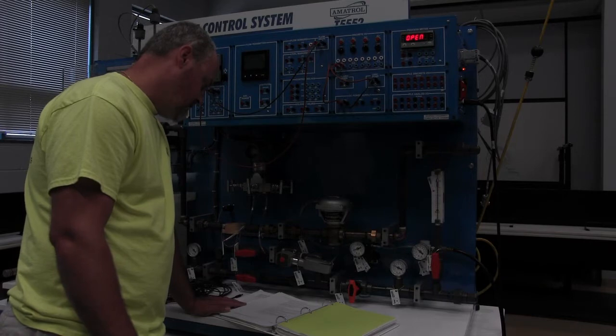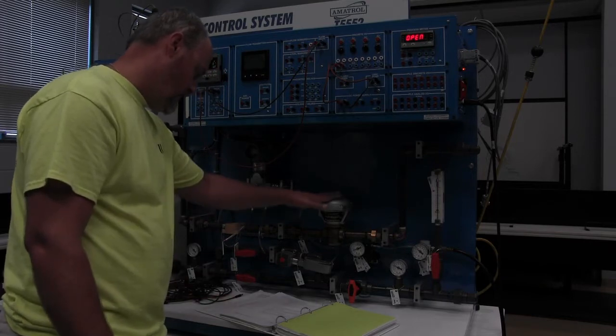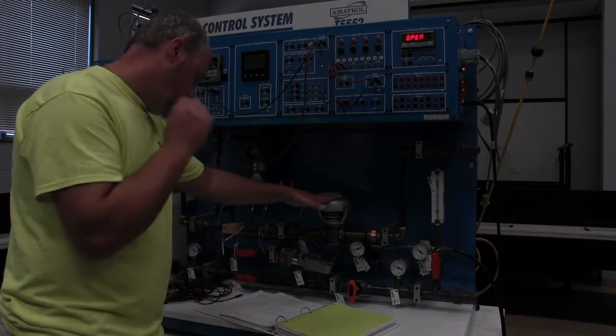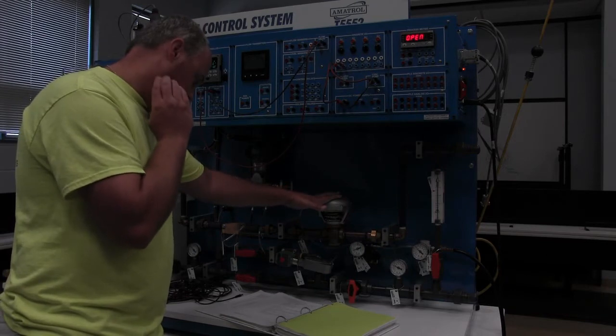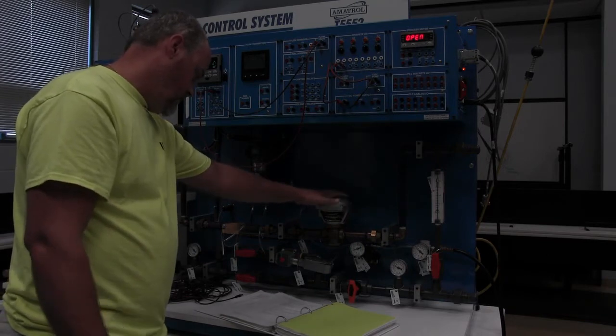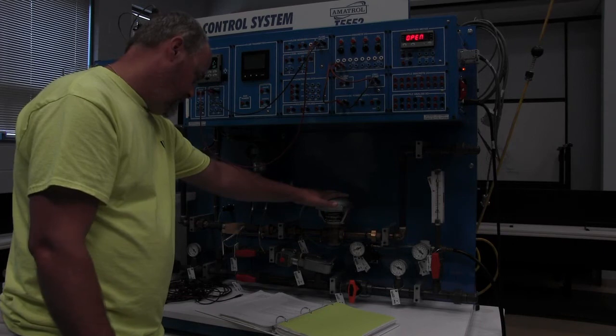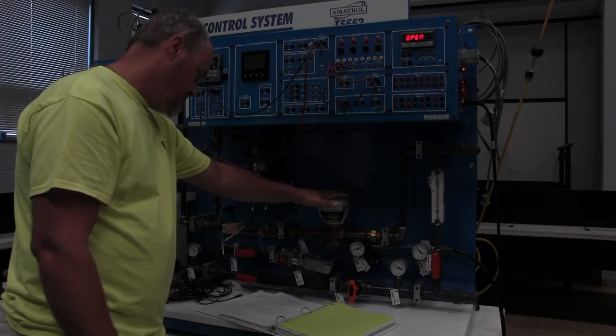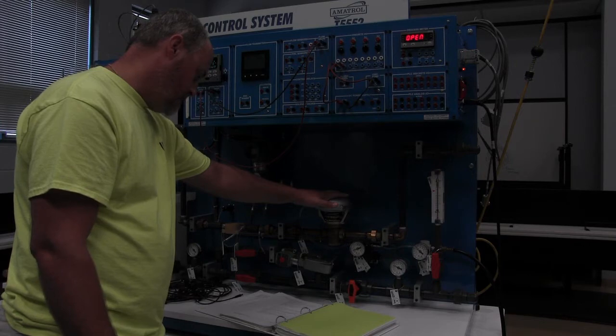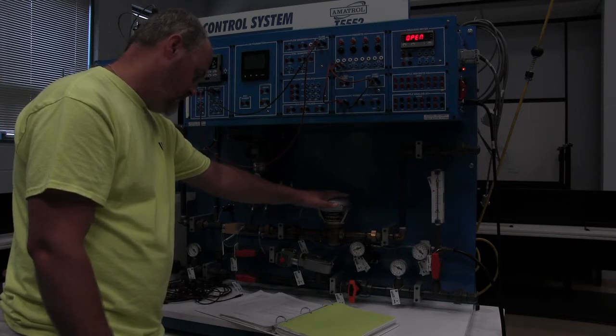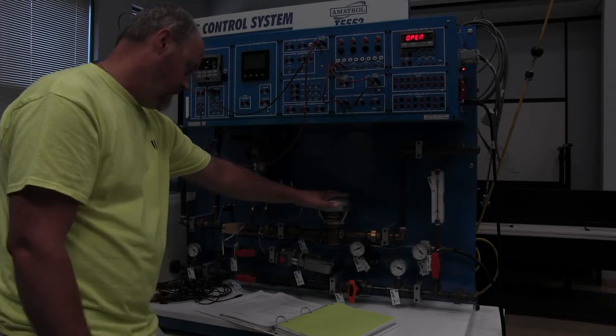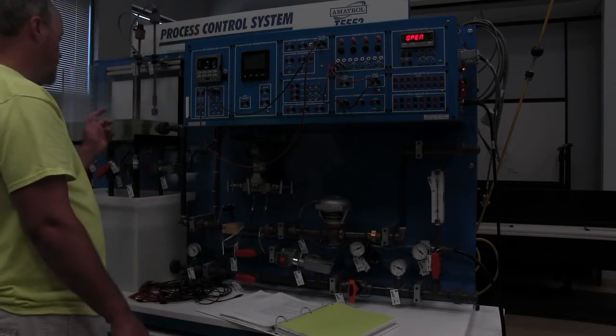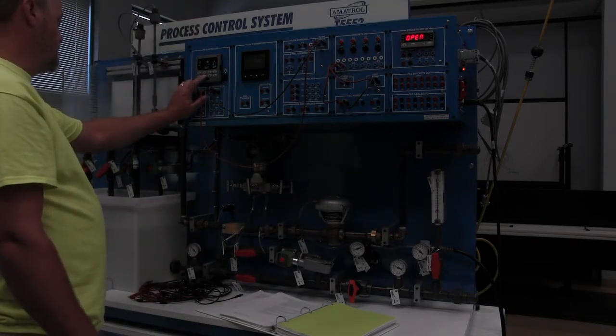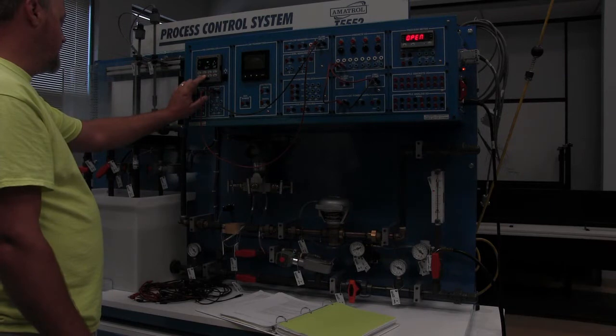Increase the output of the controller, causing the diaphragm of the control valve to close. Decreasing the controller output will cause the diaphragm to open. If the level rises above the 2-inch mark, increase the output enough to make the level drop to the desired point. If the level falls below, decrease the output to bring the water in. So we're above it now, so we're going to go ahead and start increasing this.